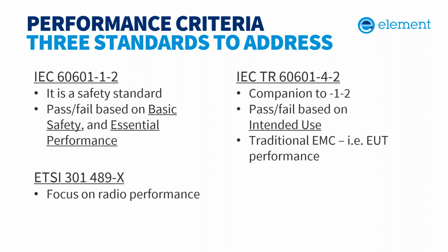So all devices that incorporate a radio fall under the Radio Equipment Directive for the EU and need to be evaluated for the performance of that radio. So for 31489, the primary concerns are that the radio doesn't unintentionally transmit, change stored data, or change its mode of operation. And this also does mean that if you've got a product with multiple radios, each one needs to be evaluated during testing. So for example, if you've got a product with Wi-Fi and RFID, both need to be active and monitored. If they can't both be active and monitored at the same time, you need to be testing them separately. So you need to do one test run with the Wi-Fi active, one test run with the RFID.